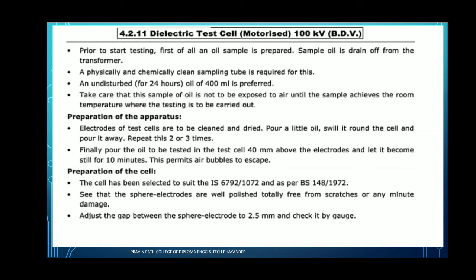Next, the dielectric test for the transformer oil of 100 kilovolt, also known as the breakdown voltage. Then we have to start the testing. First of all, the oil sample is prepared. Sample oil is drained off from the transformer. First, a physically and chemically clean sampling tube is required for this test, that is the dielectric test of the oil testing of the transformer. Take care that the oil sample is not exposed to air, and that the sample reaches the room temperature where the testing is to be carried out.